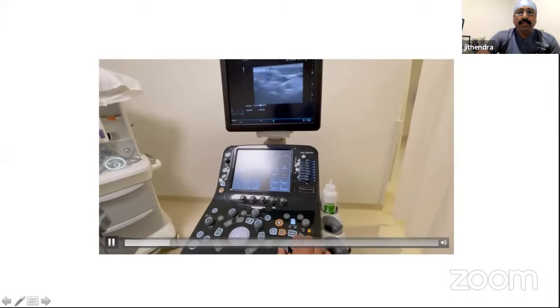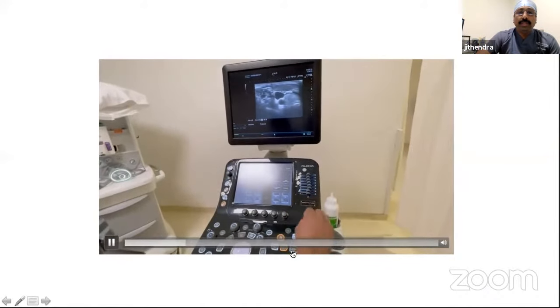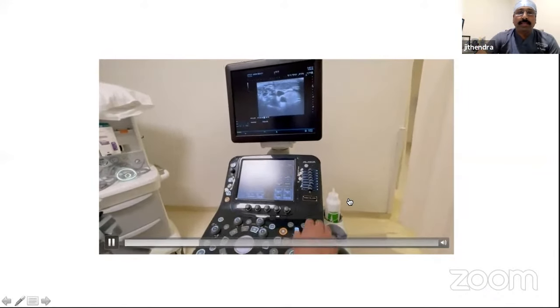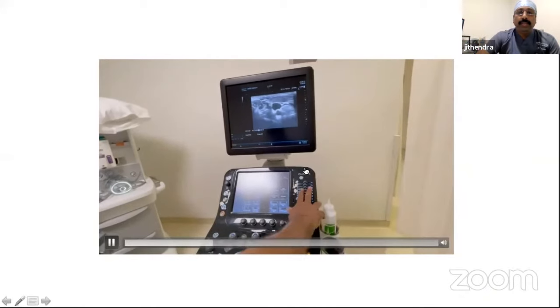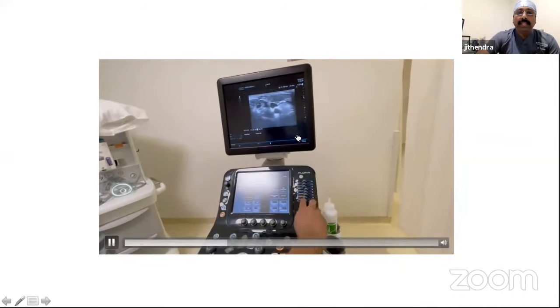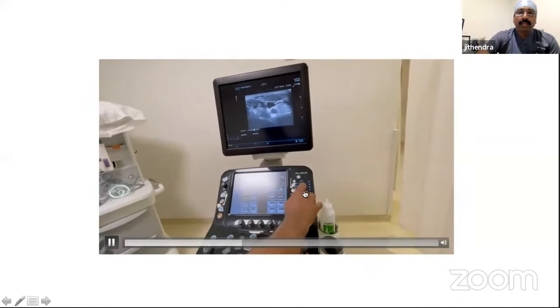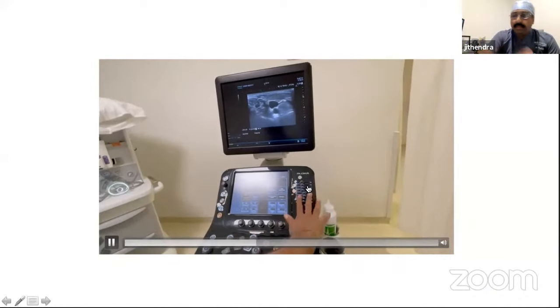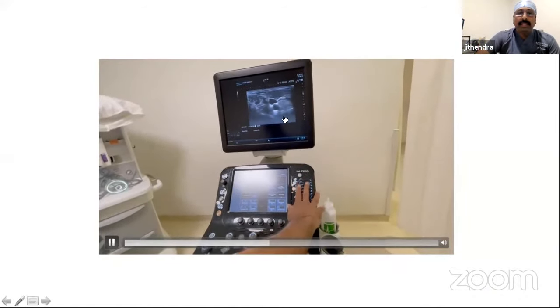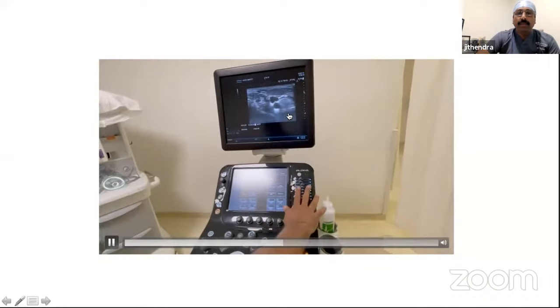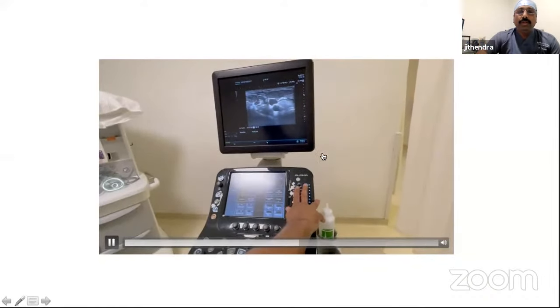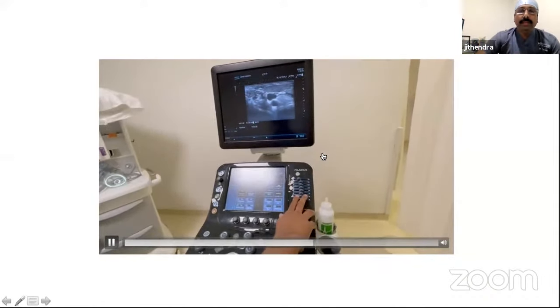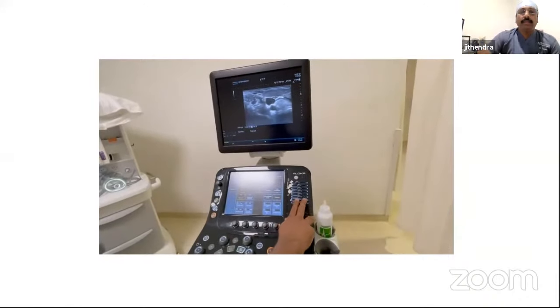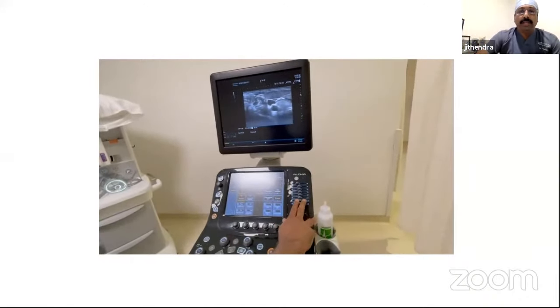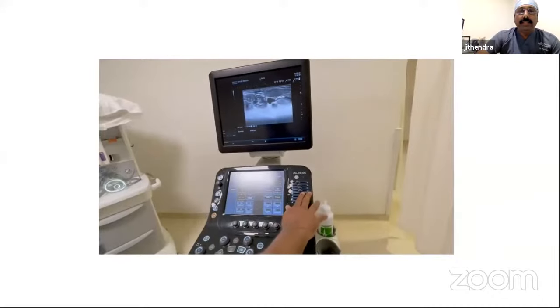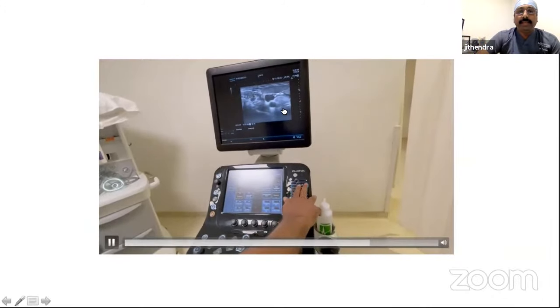This is general. The knob which is being used now is a general adjustment of the gain. And here you can individually adjust the gain at each level. So what you see here, as I move the knobs to the right side, the gain increases and it becomes more and more bright. So you need to learn to optimize the gain for the imaging of the structures for any procedure. So as I increase the gain, you can see the color, the brightness being changed at different levels.